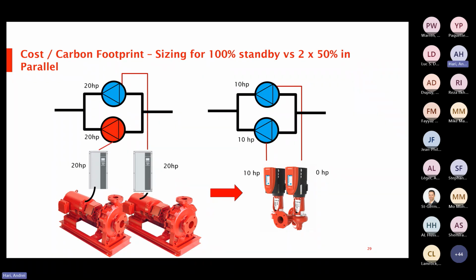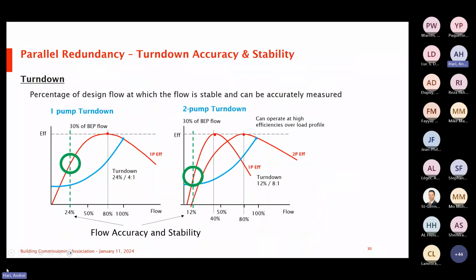So instead of doing 2 pumps, for example, at 20 horsepower each, we've done 2 pumps at 10 horsepower, 50% redundancy, but then it comes back to what we were talking about in terms of those humps and the turn down capability. Now, because I have 2 pumps, I've increased my area of peak performance in our system. And we've improved our turn down capability in that system from 24% down to 12%.